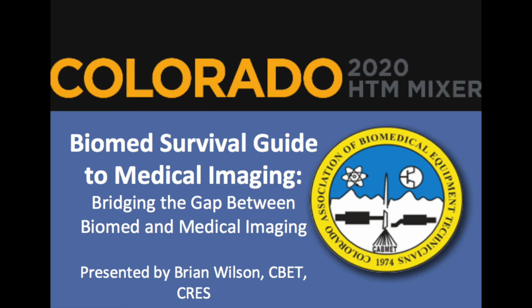PET scanners more or less do the same thing that a SPECT scanner does. The only real difference is a PET scanner costs quite a bit more and uses a different type of radioactive isotope with a really short half-life. So a PET scanner is one of those specialty things you might use to follow up on previous scans done by other machines. The isotope half-life is short, and the machines themselves are very expensive. So chances are, if you come into a nuclear medicine department, unless it's somewhere with extensive resources, you're probably going to run into SPECT cameras as your first choice of machines.